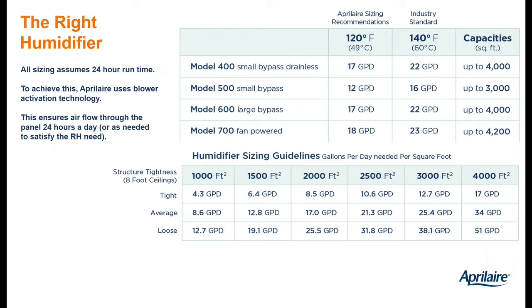And so that far right column, you can see the square footage that those humidifiers can handle, assuming 8-foot ceilings, assume a tightly constructed home. And then you see below that same chart again, just summarized so you can compare the two. So in our example, 2,000 square feet, 8-foot ceilings, tightly constructed, you can see any of the humidifiers would be able to properly humidify that home.